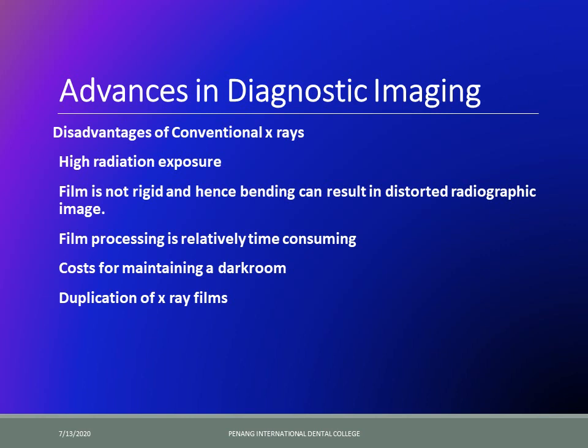Coming to advances in diagnostic imaging — the radiovisiograph has already been installed in the department of conservative dentistry and periodontics. The disadvantages of conventional x-rays — IOPA films — include higher radiation exposure; with RVG you can reduce this to one-tenth of the actual exposure. The IOPA film is not rigid, so bending can result in a distorted radiographic image, which is especially problematic in posterior areas of the mouth.